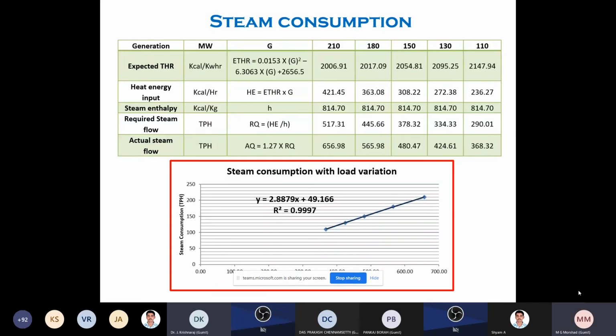Now, similarly, for fuel consumption, we can also establish the steam consumption under load variation. It is normally carried out during a PG test, but you can re-establish it. Suppose it is a 30-year-old power plant: the PG test was carried out 30 years back, in the 1980s, around 85. Now it is 2021, so there will be huge deviations. So every 5 or 6 years this should be carried out internally by the unit, so that they can establish whether their aging process is high or not, because this normally happens with aging.